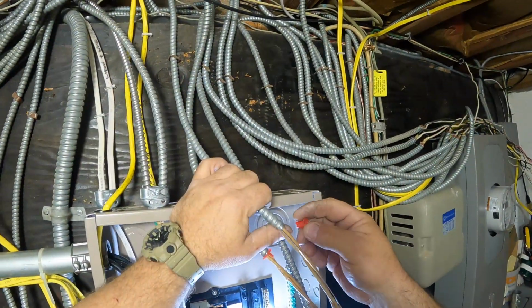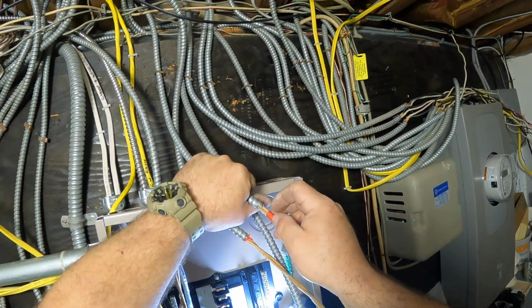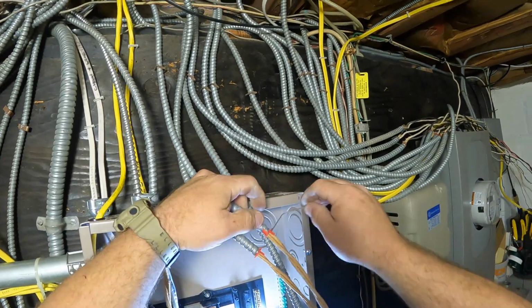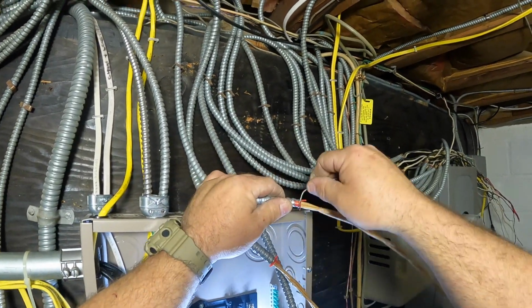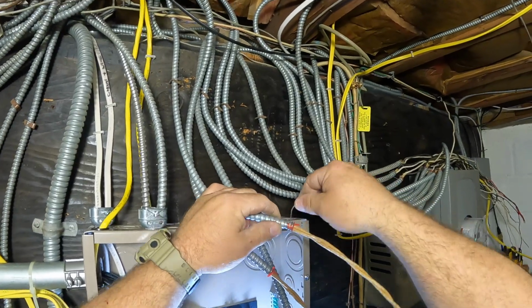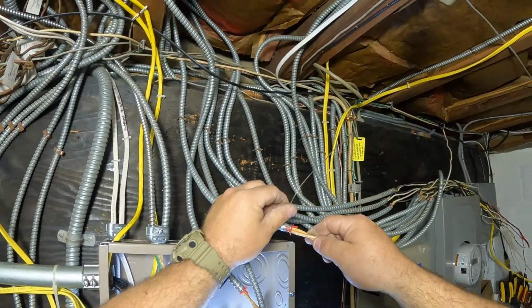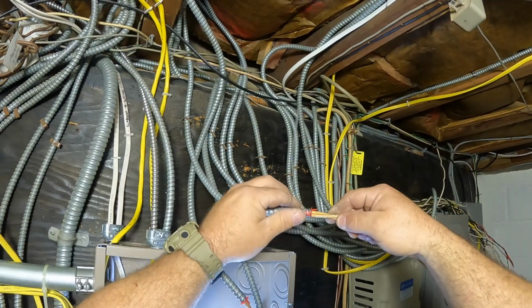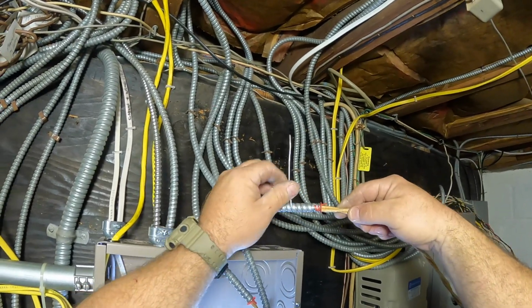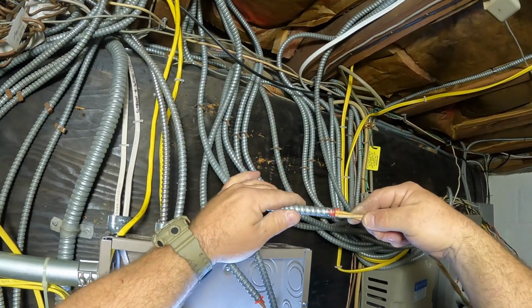Once you have the sheathing removed from the cable, you come back and you install these anti-short red heads, and you slide it up inside the cable and use this wraparound wire here that comes with the BX to attach the red head to the cable so it doesn't fall out of there. And you just wrap it around the BX cable before putting on the connector.